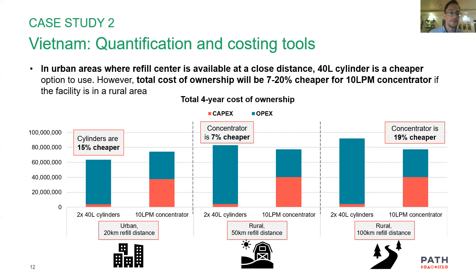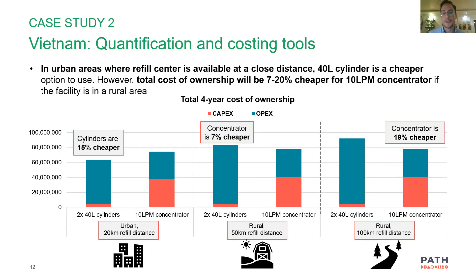In urban settings close to a refilling station, cylinders are going to be cheaper because you don't pay high delivery costs. But the farther away you are from a filling station, the more you pay for transport and logistics, so concentrators become a cheaper option. If demand increases to around four cylinders a week, concentrators become a much better long-term option because you're not paying for trucks to make repeated deliveries to the health center.